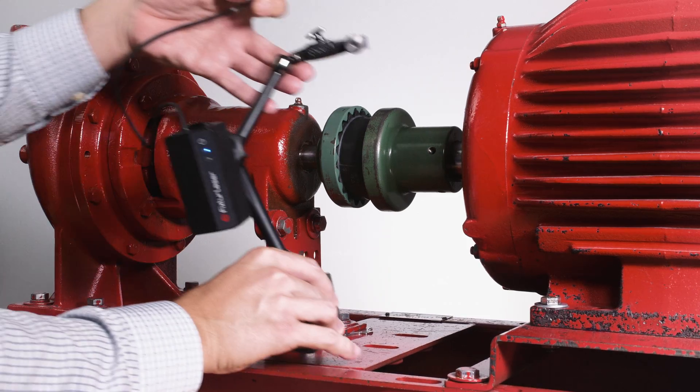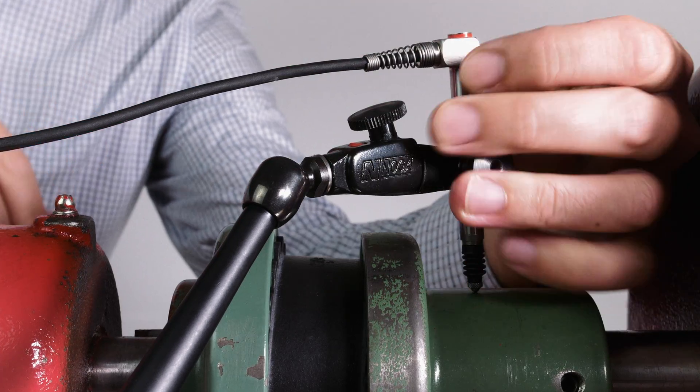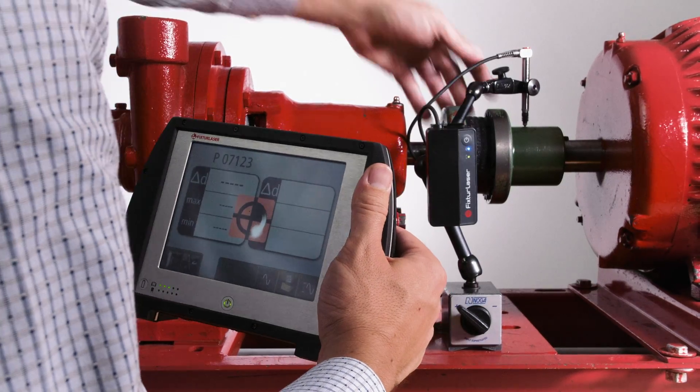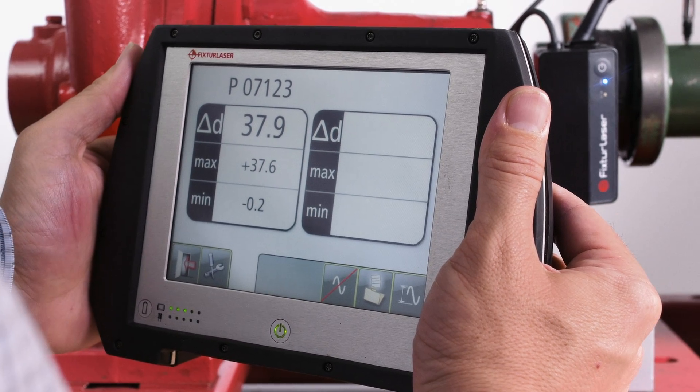In order to measure shaft runout, the probe is mounted on the articulating arm and placed in the respective position. After the press of a button and one complete rotation of the shaft by hand, the NXA will give results.